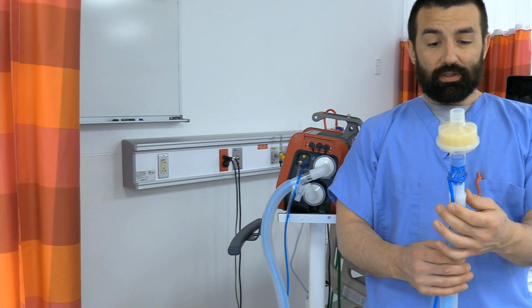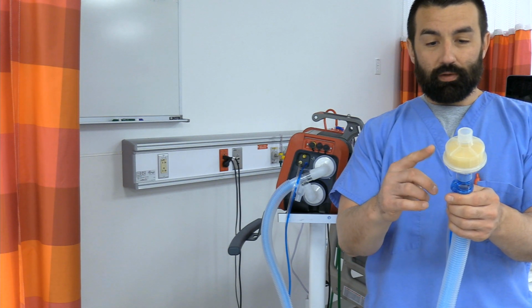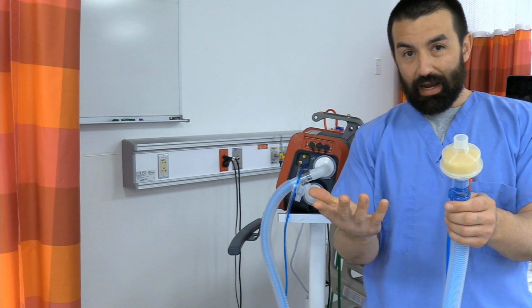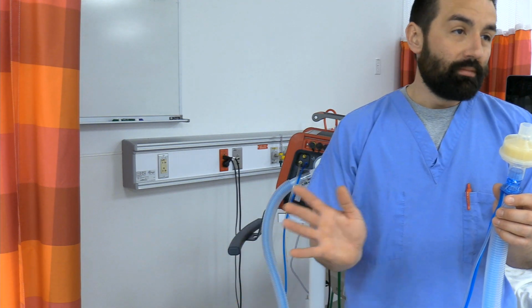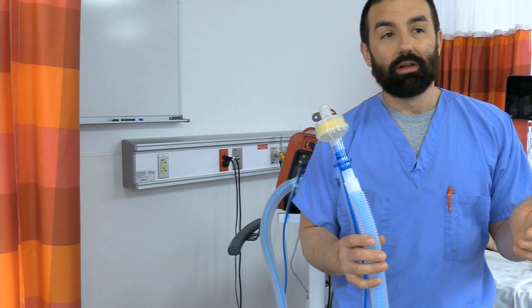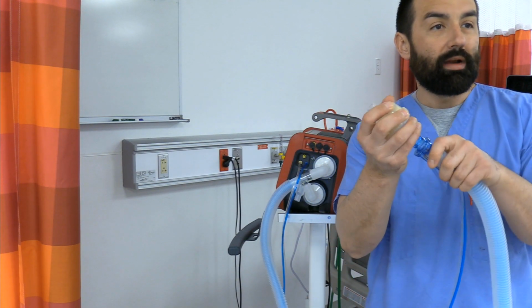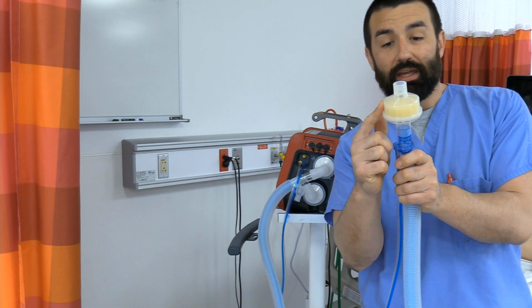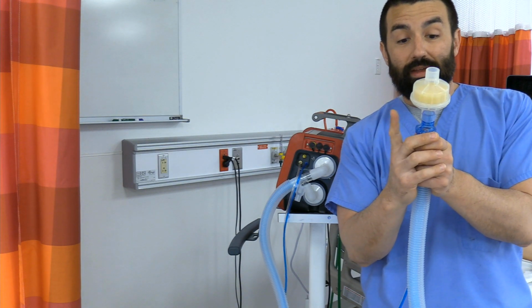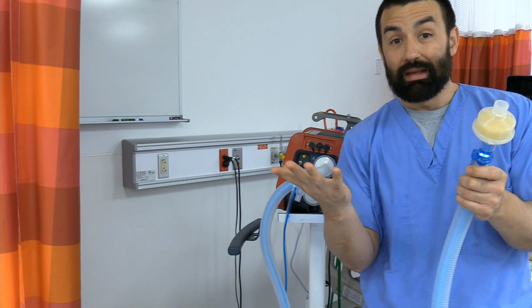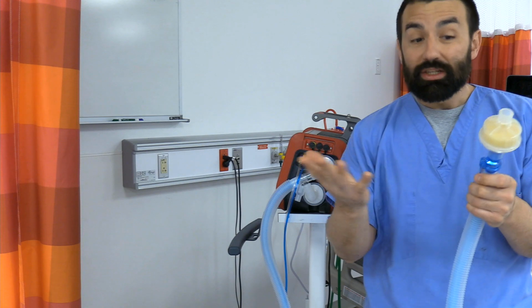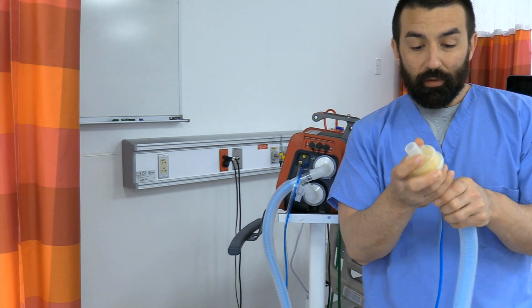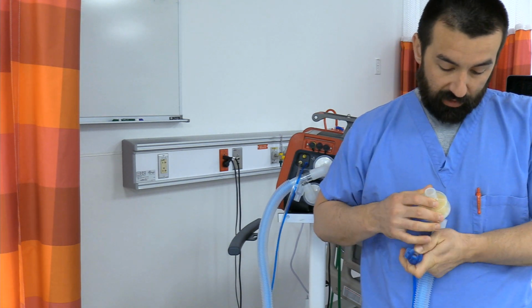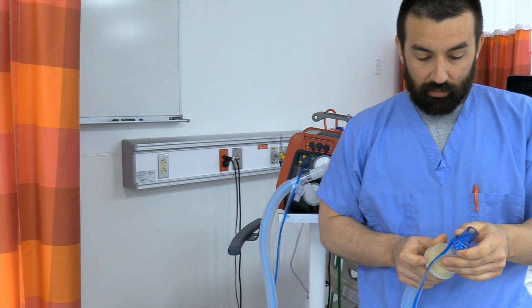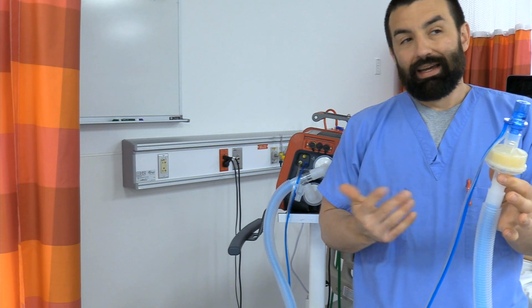Technically, you'll see people say one of two ways as far as where to put that flow sensor. Their flow sensors hold up to condensation and mucus and all sorts of stuff, but I'm still a little leery. Whenever I can, I'll typically try and put the HME between the patient and the flow sensor here. It gives me an extra little bit of protection if something bad happens. I've had people that go, well, you want that flow sensor closest to the patient, which I wouldn't refute, and people will hook it up like this.